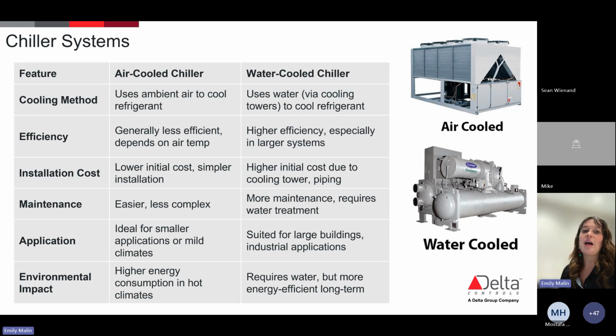We generally see that water-cooled chillers are going to have a higher efficiency. They will probably have a higher initial cost just due to that cooling tower, because you're going to have a lot of piping happening in there. Usually you're going to see this for larger buildings and more industrial applications. The applications for an air-cooled chiller are usually a little bit smaller, and you might have higher energy consumption in hotter climates with air-cooled chillers.